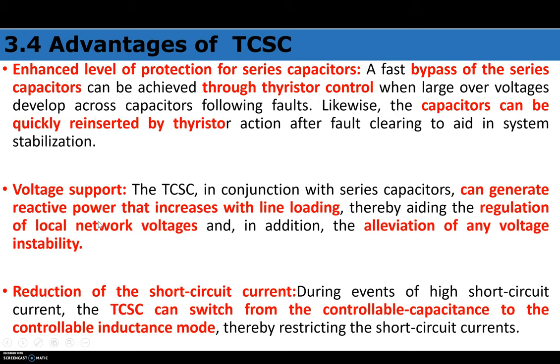Voltage support is also a benefit of TCSC. In conjunction with the series capacitor, TCSC can generate reactive power that increases with line loading, thereby aiding the regulation of local network voltages and alleviating any voltage instability. The fixed capacitor in series compensates the reactance of the transmission line, reducing the reactive power demand or providing the additional reactive power needed by the system.